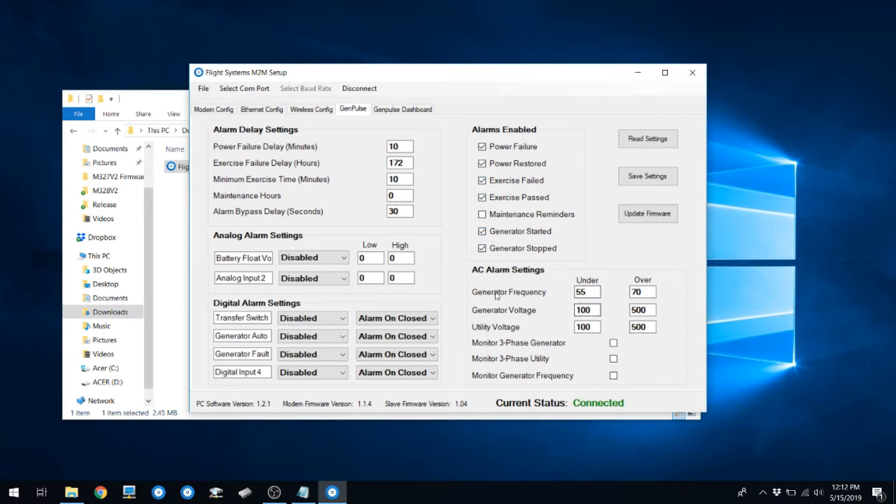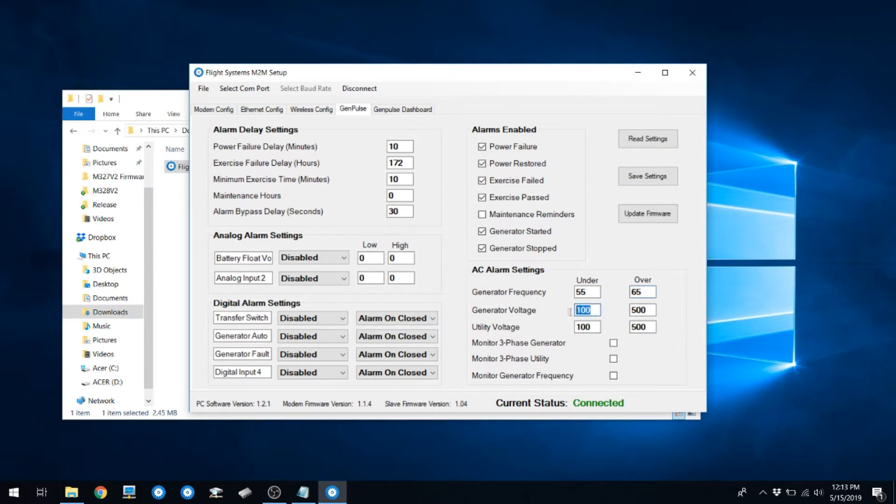You can also verify your generator under and over frequency settings, along with the generator voltage under and over and utility voltage over and under. Make sure you set these for reasonable values based on your line configuration.